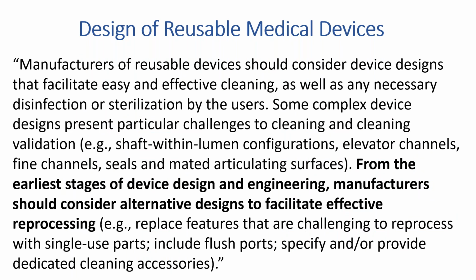So part of it is the design of reusable medical devices. It says, quote, manufacturers of reusable devices should consider device design that facilitates easy and effective cleaning, as well as any necessary disinfection or sterilization by the user. And it says that some complex device designs present particular challenges to cleaning and cleaning validation. For example, a shaft within a lumen configuration, elevator channels, fine channels, seals, and mated articulation surfaces.